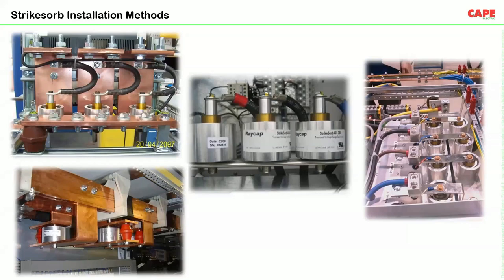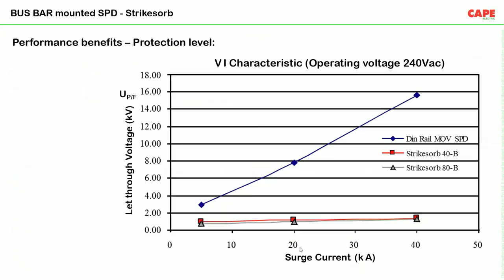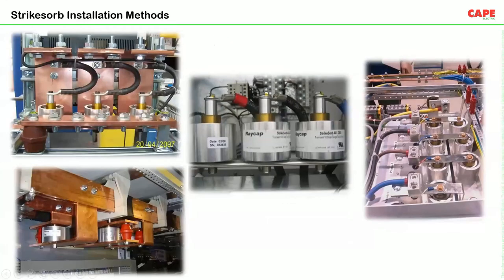In this particular case, in the picture on the top left side, you can see the length of the wire. There is a wire used, but the length of the wire is too short, maybe about 200 millimeters. From the bus bar, it is directly connected to the terminal, and the earth terminal is directly on the bus bar. In figure number two, left side bottom, you can very well see the SPD is connected in between the bus bars. In case number three, of course a wire length is used, but we have to ensure that this wire is very short. So these are some of the typical ways of installing.